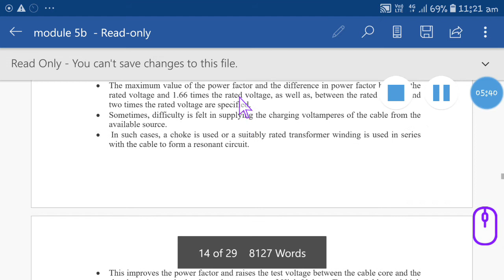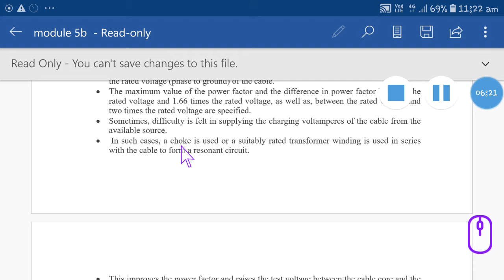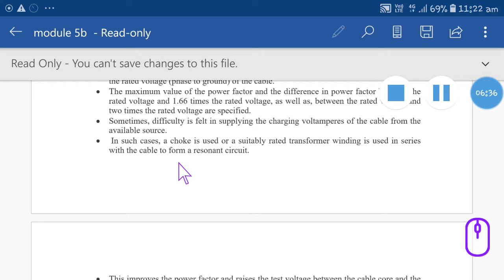So at that time the cables have to be connected along with chokes. Chokes are used, or a suitable rated transformer. Either they may use a choke or a suitable rated transformer, and whatever transformer winding there is, they will connect in series with the cables. Sometimes they may feel difficulty in supplying the power, the volt-ampere, to the cables from the available source. At that time these are used in series with the transformer windings during testing.